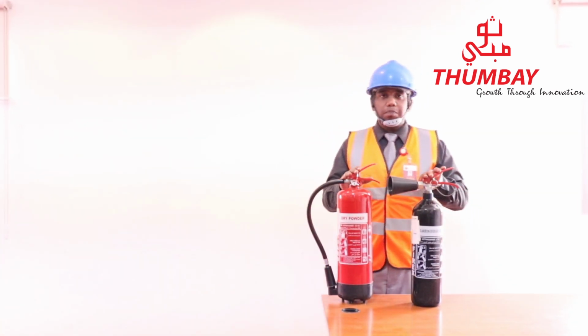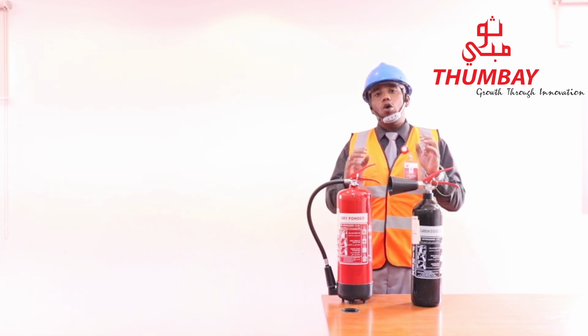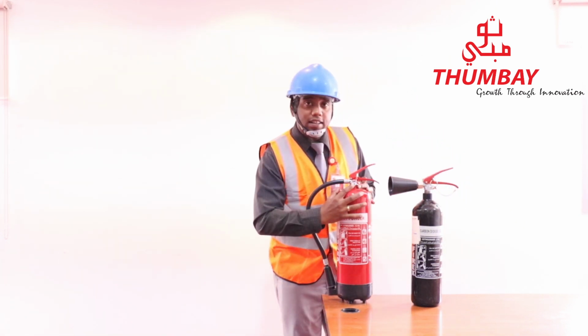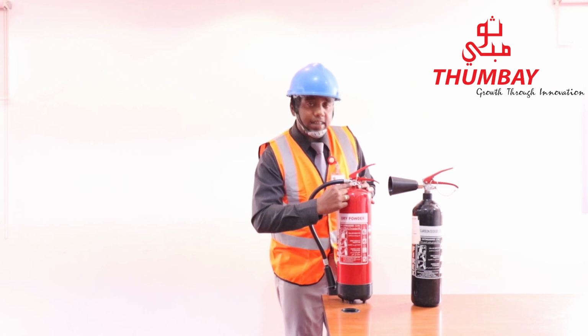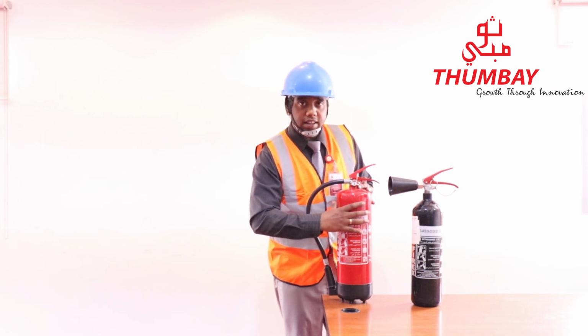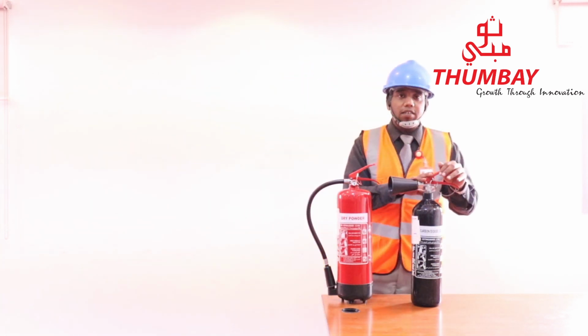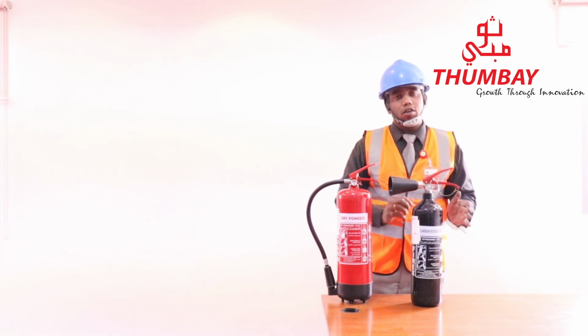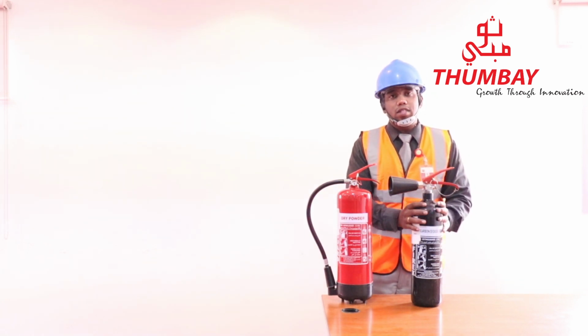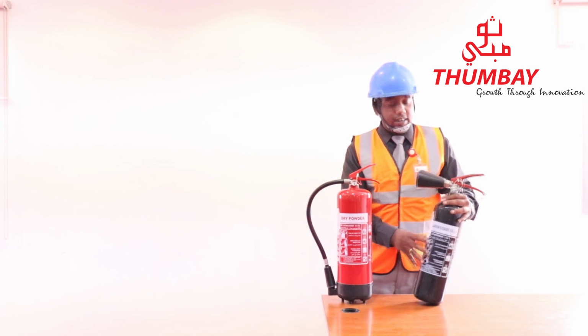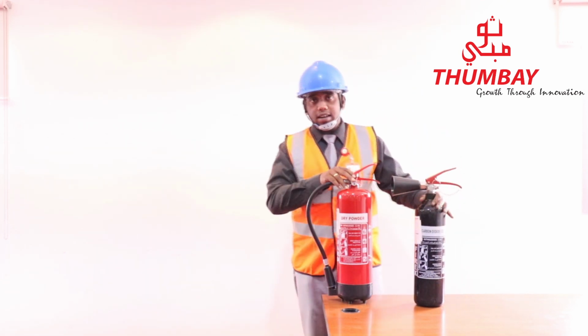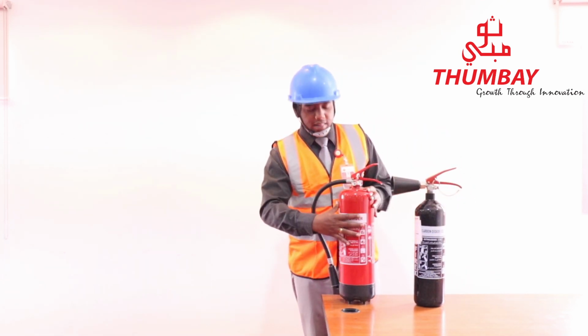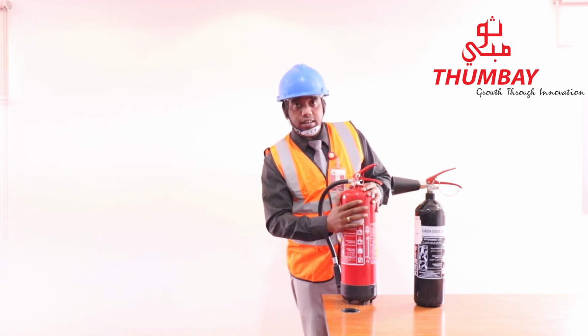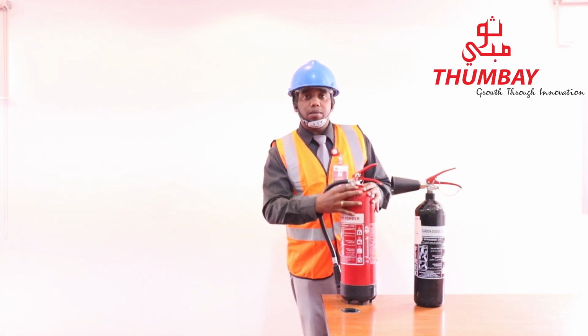So how can we find out the basic difference between these cylinders? Can you see there is a pressure gauge? The pressure gauge indicates the pressure inside the cylinder. The carbon dioxide cylinder will not have any kind of pressure gauge, because it can be tested only using a hydrostatic method in an industrial way. But with this one, you can see from outside what the pressure is and what the contents are.